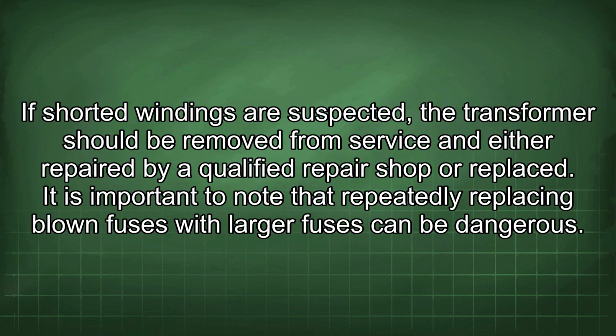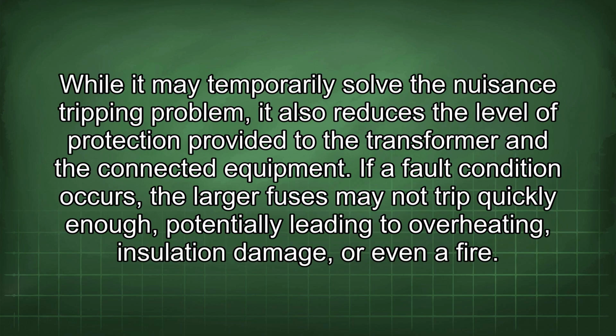If shorted windings are suspected, the transformer should be removed from service and either repaired by a qualified repair shop or replaced. It is important to note that repeatedly replacing blown fuses with larger fuses can be dangerous. While it may temporarily solve the nuisance tripping problem, it also reduces the level of protection provided to the transformer and the connected equipment. If a fault condition occurs, the larger fuses may not trip quickly enough, potentially leading to overheating, insulation damage, or even a fire.